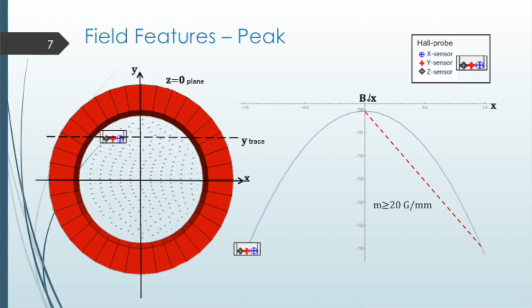Well, here's a picture of a Hall probe sensor, a Hall probe itself, and we have 3 sensors. Now, in this particular case, we want to find the X sensor's location along the X-axis. So on the right here, we have a picture of the magnetic field measured by this X sensor. So as we scan across this magnetic jig, we can see that the X sensor magnetic field that it's measuring actually varies as a peak. So if we can align it to the peak value, we can determine the X sensor location as being at X equals 0 with respect to the magnetic jig.